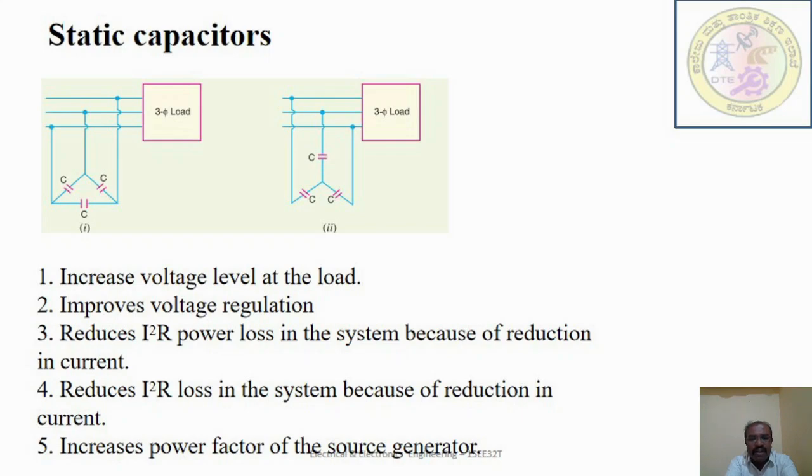Static power factor correction can be applied at each individual motor by connecting the correction capacitor to the motor stator. A disadvantage can occur when the load on the motor changes and can result in under or over correction.